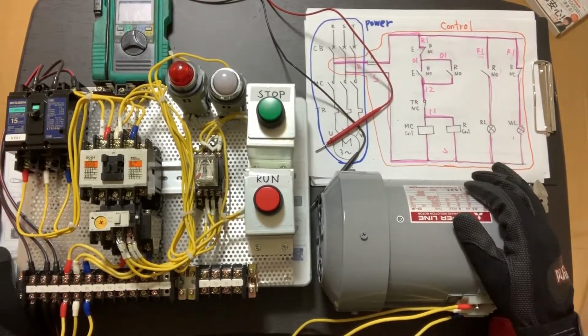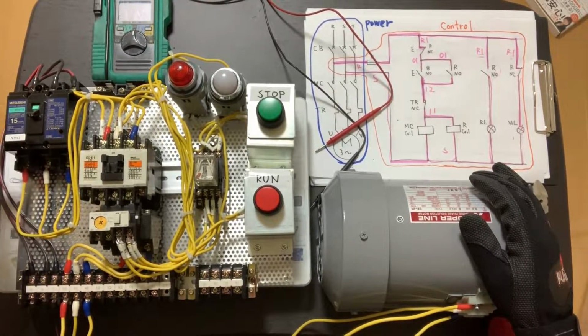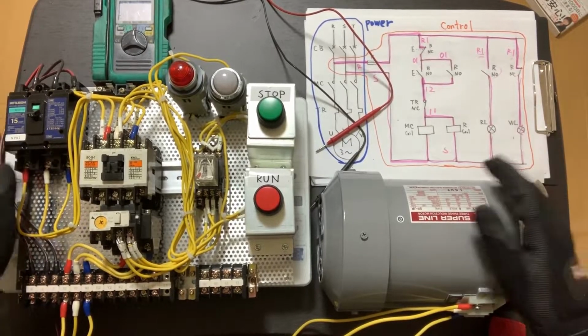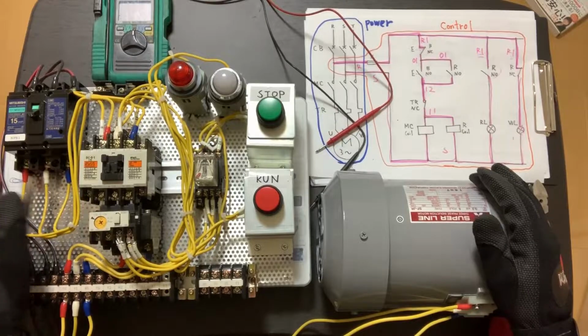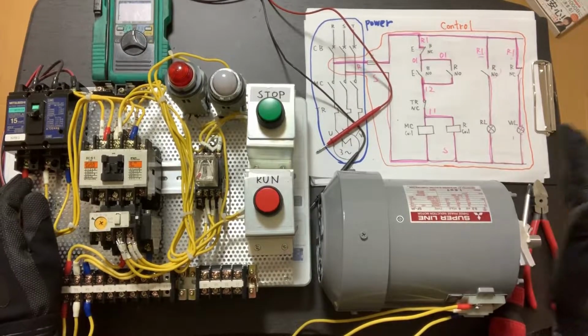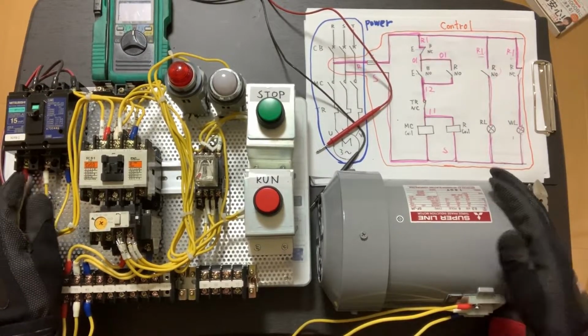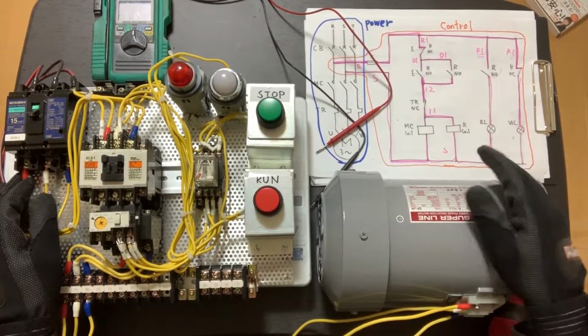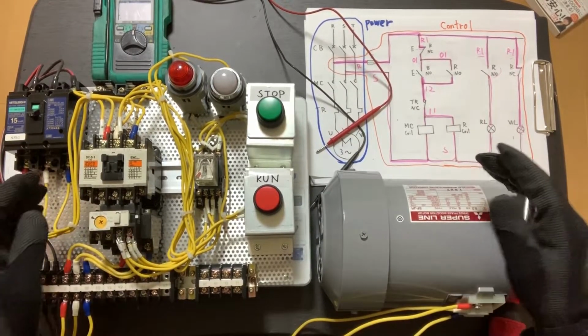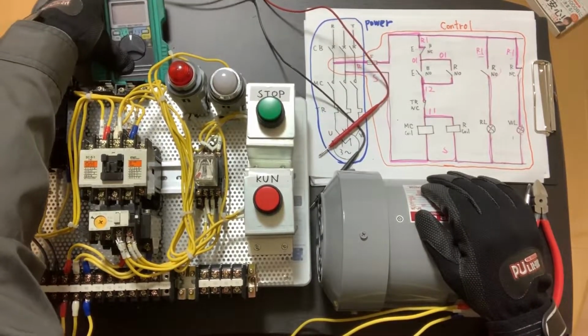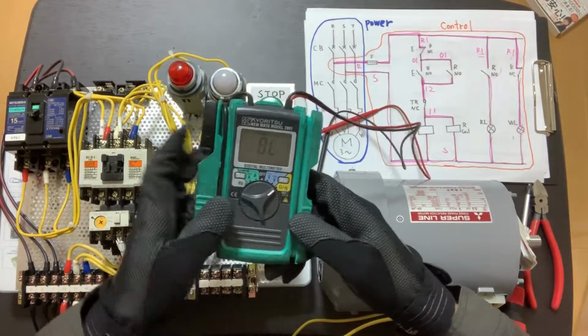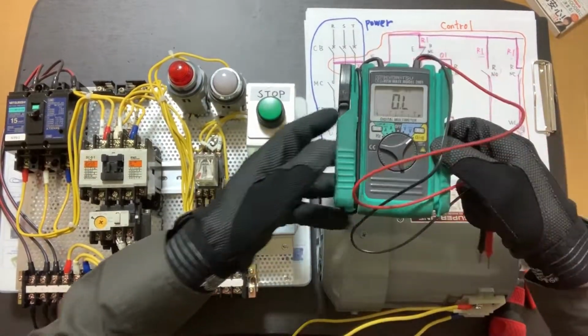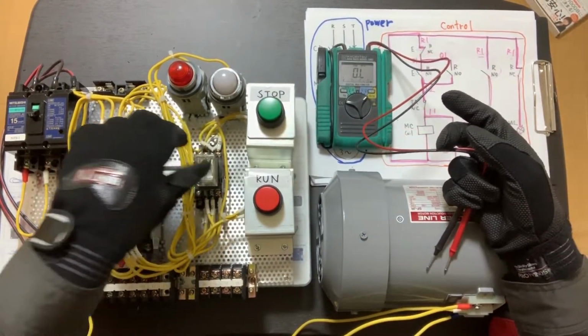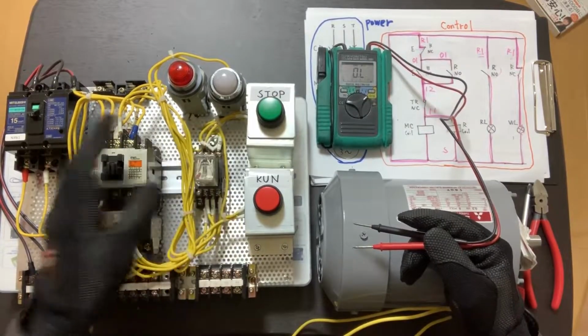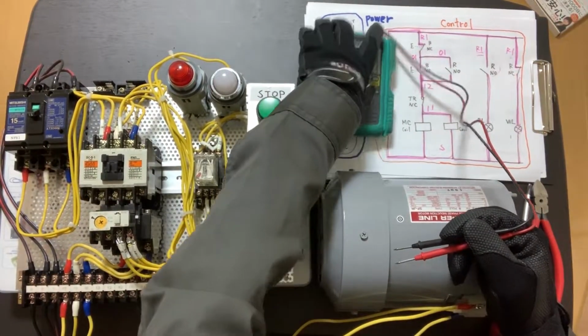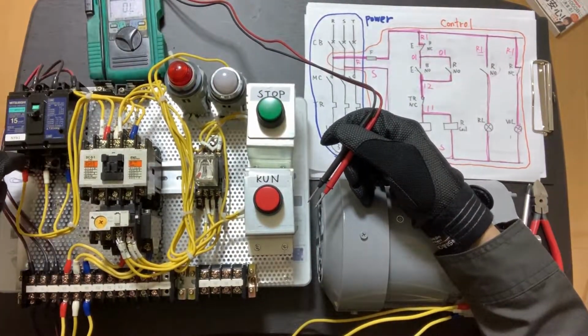Okay, all wiring is done. However, please don't apply power before some safety confirmation. We need to confirm there is no failure, like a short circuit or a ground fault. Sometimes such dangerous failures happen because of long wiring. You can check for a short circuit with a multimeter in the resistance range, the same as the confirmation of the contacts of a relay or magnetic contactor.